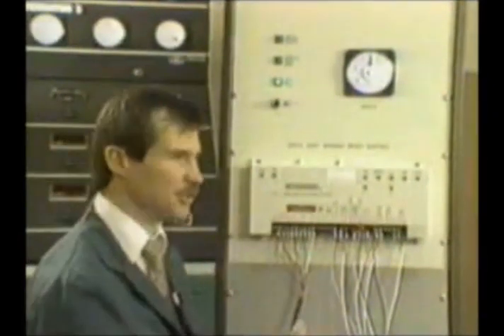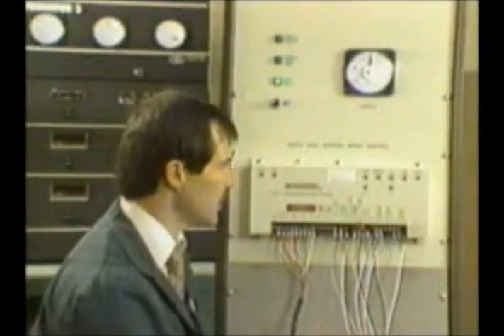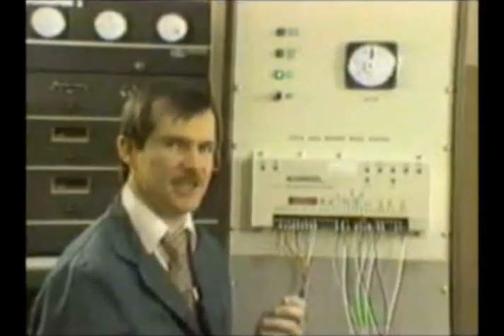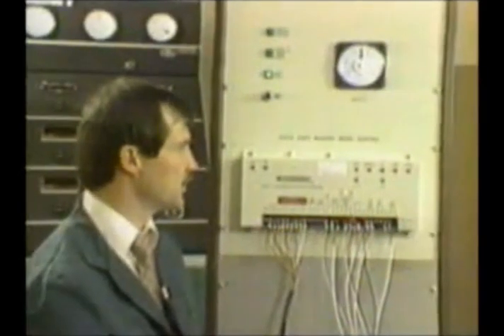So now we've set our idle speed, we've set our ramp time. We showed you how to adjust your gain and reset. We showed you how to set your rated speed pot. One more comment on the gain and reset potentiometers. Not always do you want optimum gain and reset settings. If you're running in a large system where you have 2, 3, 4 engines load sharing, setting each engine at optimum response time could cause an instability once you start putting the units together. So you might need to crank off on your gain a little bit there in a large system. So just a word to the wise there. If you're having a problem once you hook engines together, cut back on the response a little bit of each unit.